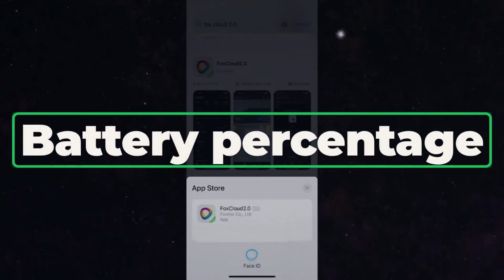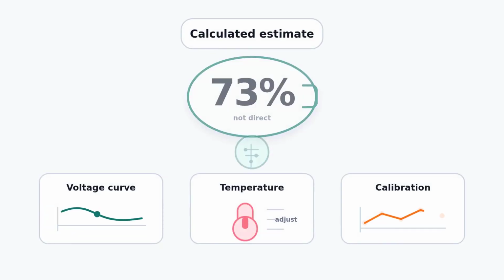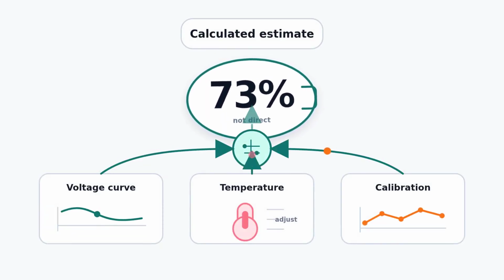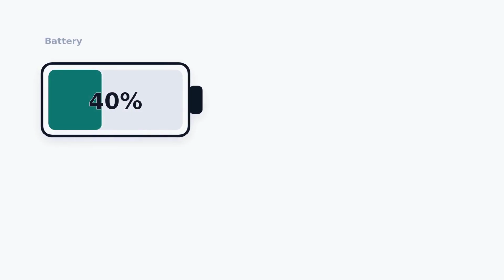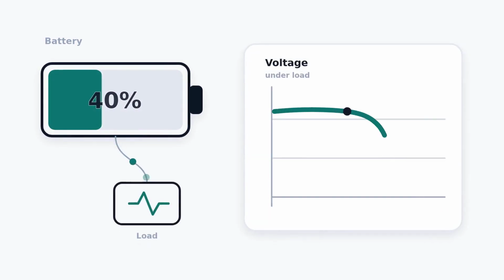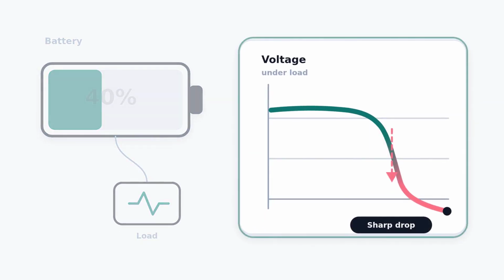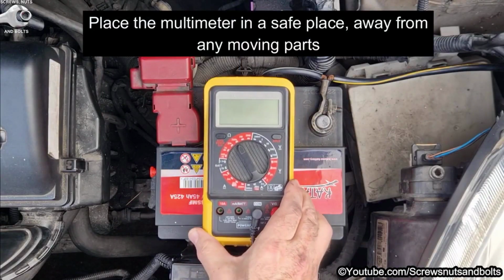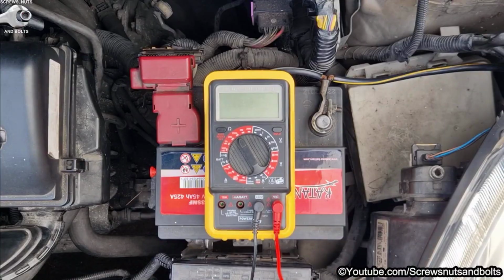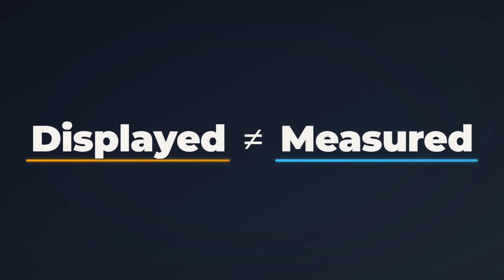The deeper shift here is this. Stop treating battery percentage as a reliable readout. It is an estimate built on voltage curves, temperature compensation, and calibration history. When a system shuts off at 40%, the percentage was never the true story. Voltage under load was. That is what the test actually measures. The percentage is not the measurement. It is the interpretation, and as you have seen, the interpretation can be wrong by 30% before anything flags an error.